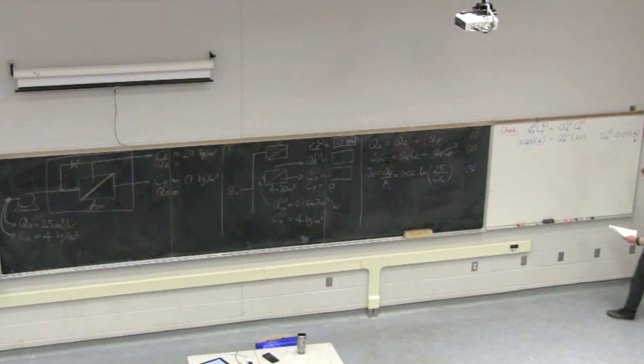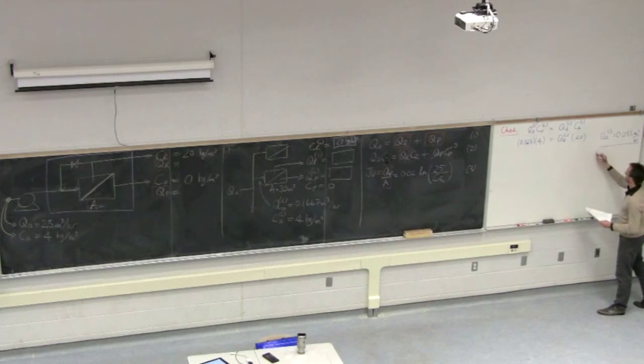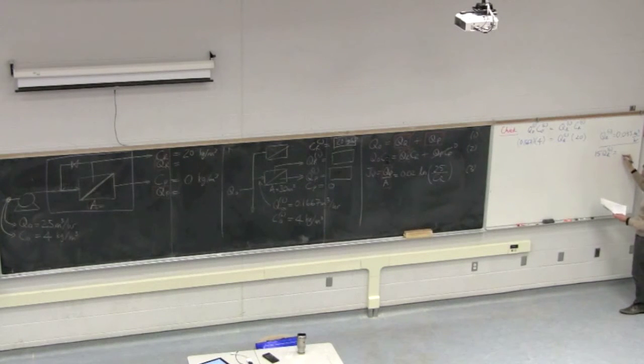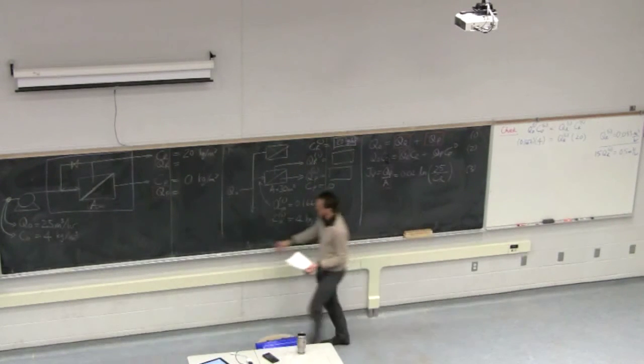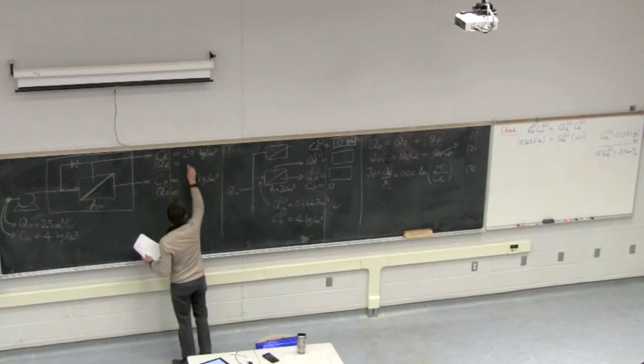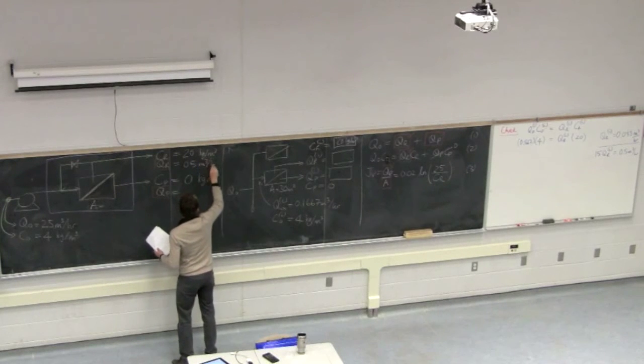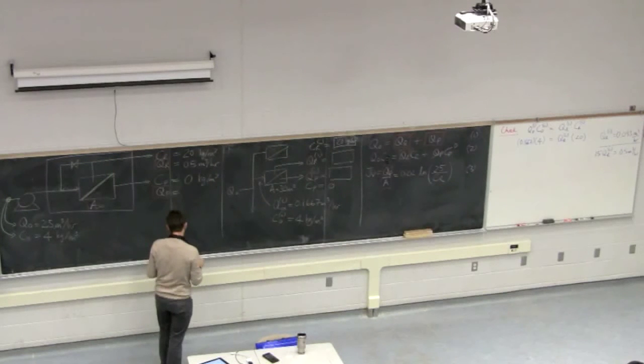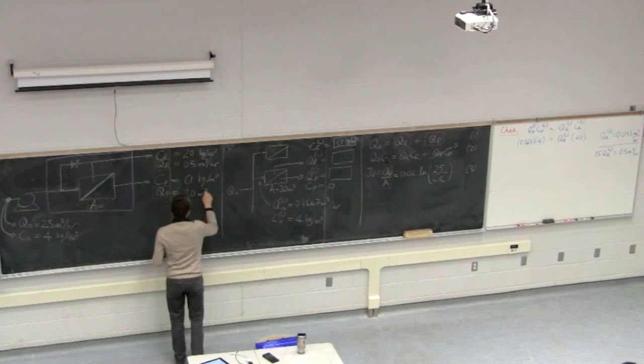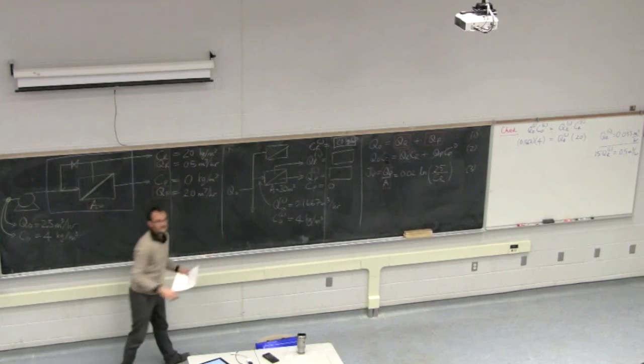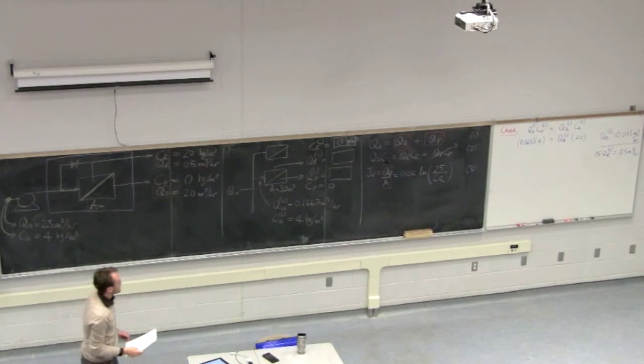And if we check there, if we're going to do this over 15 membranes, we're going to recombine that retentate flow rate 15 times. So 15 times QRi gets you back to 0.5 meters cubed per hour, which is what our original QR was. In fact, I'll just quickly rewrite up here what they were so we can cross-check. So this was 0.5 meters cubed per hour, and QP was 0.5. Okay, so that check worked.